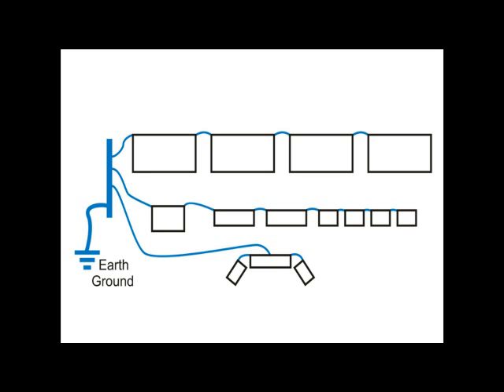There are no ground loops in this drawing, but if a new piece of equipment is installed like this, you can see that there are now two ground connections, and those connections cause a ground loop.